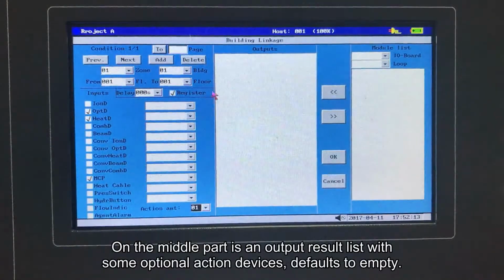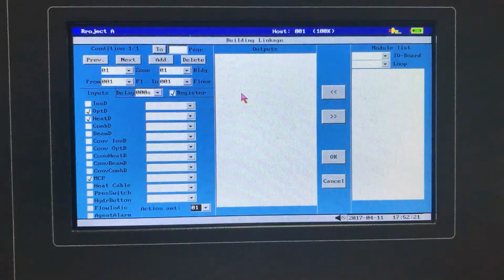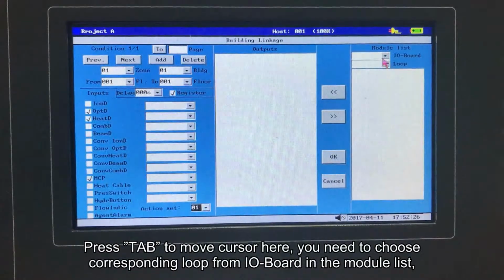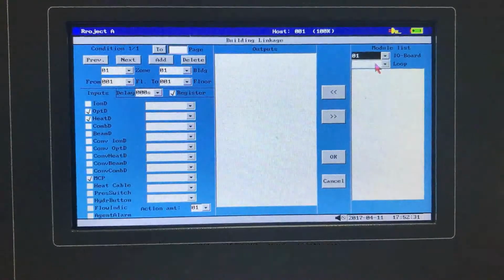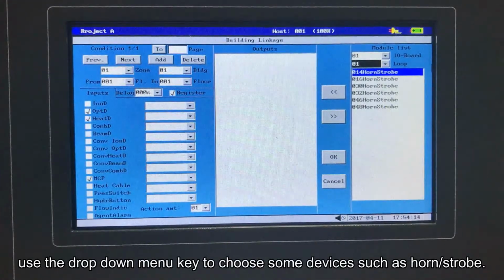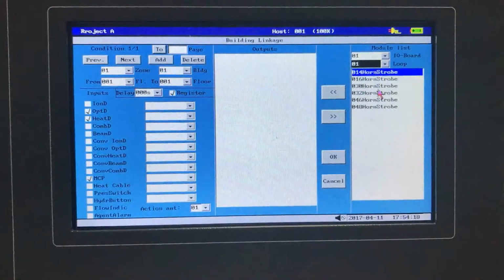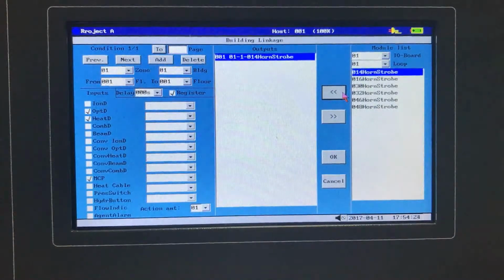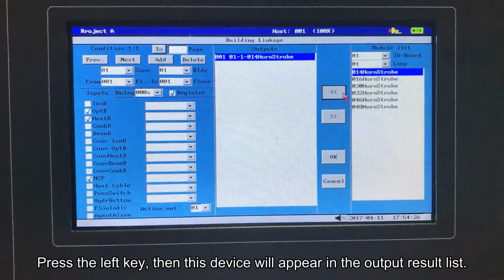In the middle part is an output result list with some optional action devices. Defaults to empty. Module list. Press Tab to move the cursor here. You need to choose the corresponding loop from the I/O board in the module list. Use the drop-down menu key to choose some devices, such as horn and strobe. Press the left key, and this device will appear in the output result list.